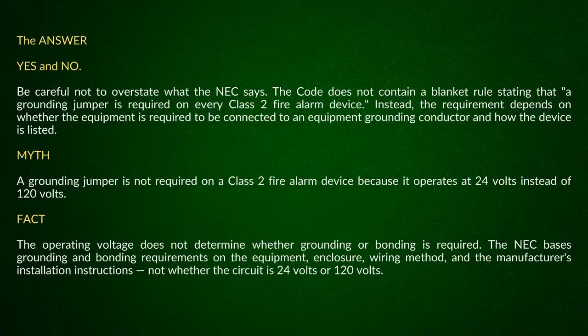And then when you look at 250.110, what does that deal with? That's all your different equipment that's required to be connected by an equipment grounding conductor. True, and that's kind of, I think, where this gray area comes into, because there is no equipment grounding conductor for this system.